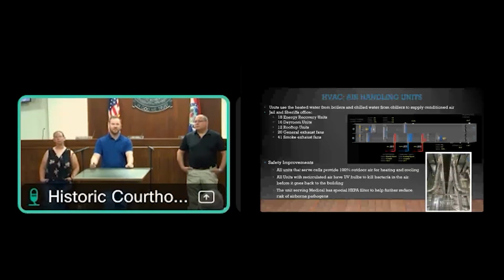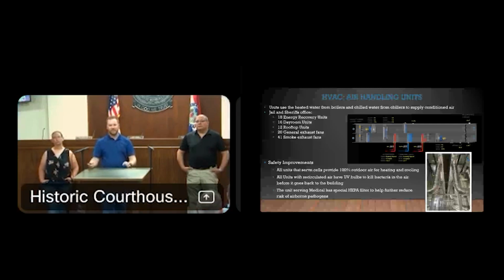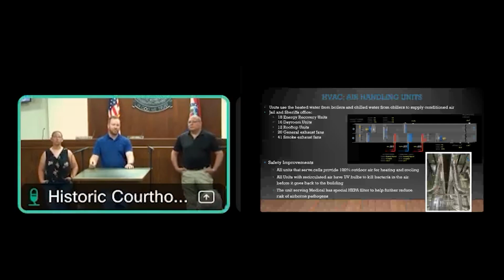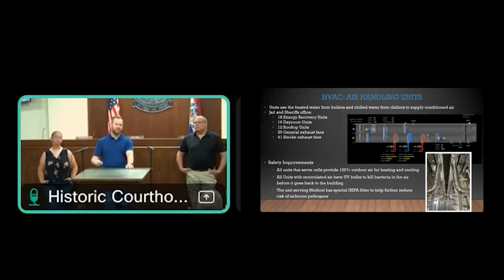And then the next component of our boilers and chillers is our air handling units. So you can see how many we have. We have 18 ERU, 16 day room, 12 rooftops, and then over 60 exhaust fans. And one of the good things compared to our old jail, all the units that serve cells at the jail are 100% outdoor air. So they have an ERU, or energy recovery wheel, that turns all the time, that absorbs some of the cooling or heating capacity that's in the building, and it exhausts that and then puts 100% fresh air into the building.